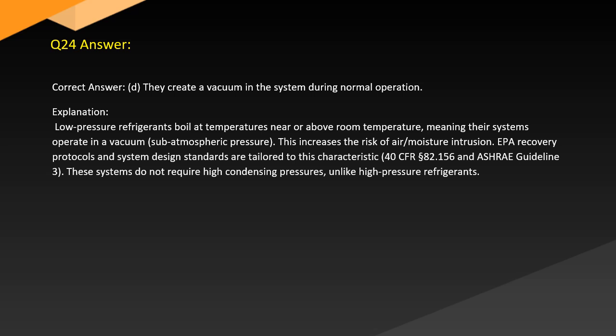Answer. Correct answer: D. They create a vacuum in the system during normal operation. Explanation. Low-pressure refrigerants boil at temperatures near or above room temperature, meaning their systems operate in a vacuum, at subatmospheric pressure. This increases the risk of air and moisture intrusion. EPA recovery protocols and system design standards are tailored to this characteristic.